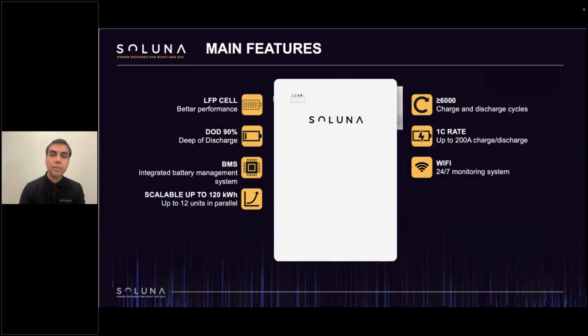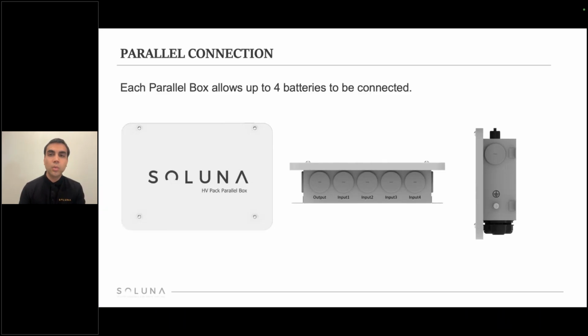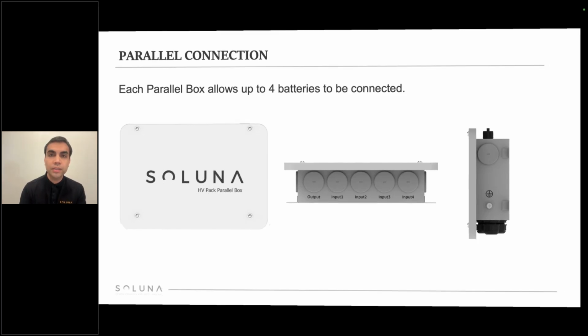And it's scalable up to 120 kilowatt hours. You have the ability to parallel up to 12 units using the parallel box, which allows you to connect up to 4 batteries. So you will have 3 parallel boxes for 4 batteries each, and that will allow you to have 12 batteries. One will be the master parallel box, which will have the data logger, and one data logger will be able to send all the information of the 12 batteries.